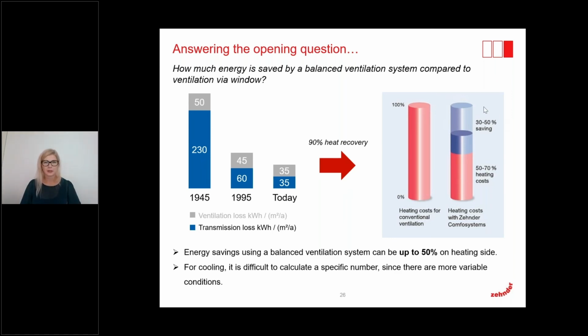And nowadays the transmission losses and the heat losses for ventilation are more or less equalizing. But if we have ventilation systems with heat recovery around 90%, this in the end affects our overall heating costs, with savings of up to 50%. And this is a very high portion. If you think about it, if we can reduce something by half, this is significant financially and also for the comfort as well.